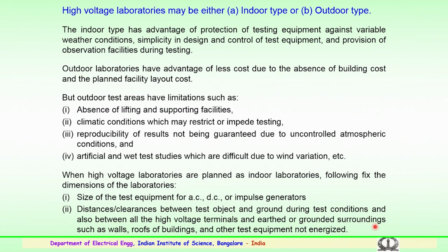So, when high voltage laboratories are planned as indoor laboratories, it is important to see that the following points are considered. Like the size of the test equipment: in an indoor hall, the laboratory has to be planned depending upon the size of the test equipment. This could be for AC, DC or impulse generators.